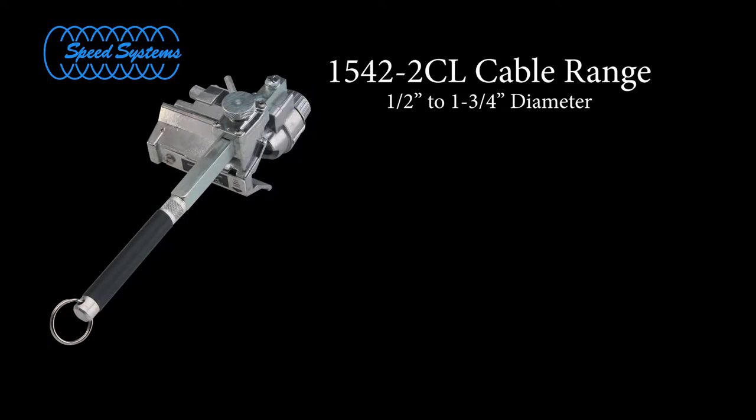The 1542 series strippers are designed for cables from 1/2 inch to 1-3/4 inches in diameter over the Semicon shield. This roughly translates to 1000 MCM and smaller when stripping 5KV cable.